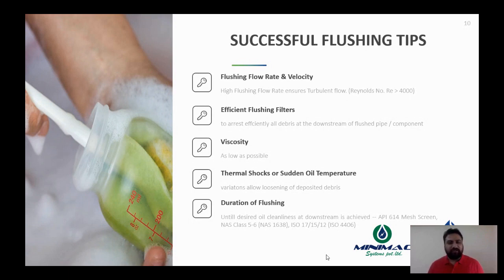Filters or an efficient filtration system while flushing is again very important. By efficiency, I mean the micron rating, the life of filters, and the flow rate of filters. I've seen a lot of sites using lower capacity filters, and then people scratch their heads over how to replace these filters again and again.